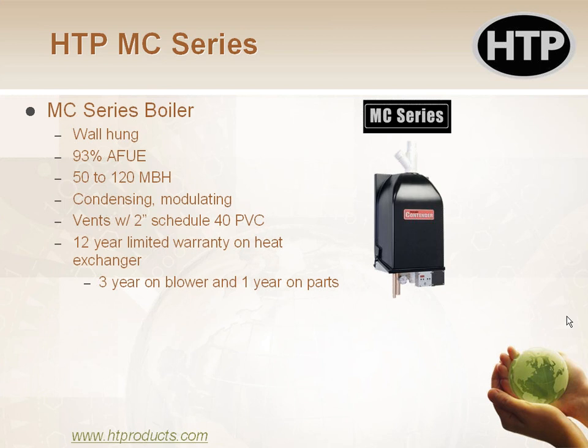They are condensing and modulating boilers. So if you're not familiar with those terms, condensing, just like with a condensing furnace, it means we're going to allow some of the flue gases to actually condense and run back into either a secondary heat exchanger or to the backside of the original heat exchanger and reclaim some of that energy, right? Because these flue gases are condensing, we can't do that on a traditional cast iron boiler. It'd be too corrosive. So we have to use stainless steel or aluminum or titanium or some other metal like that. In this case, these are stainless steel heat exchangers in these boilers here.